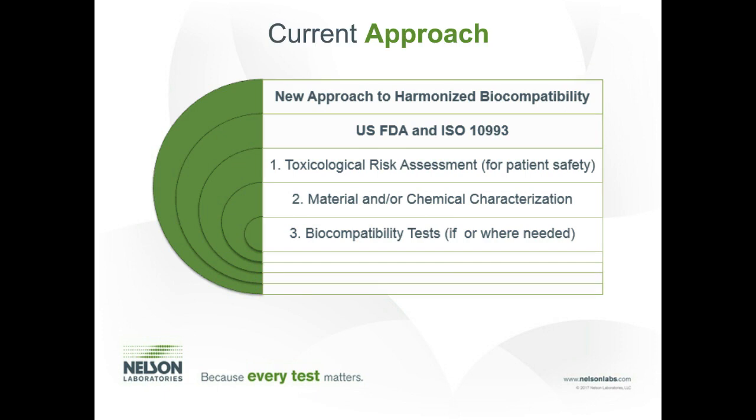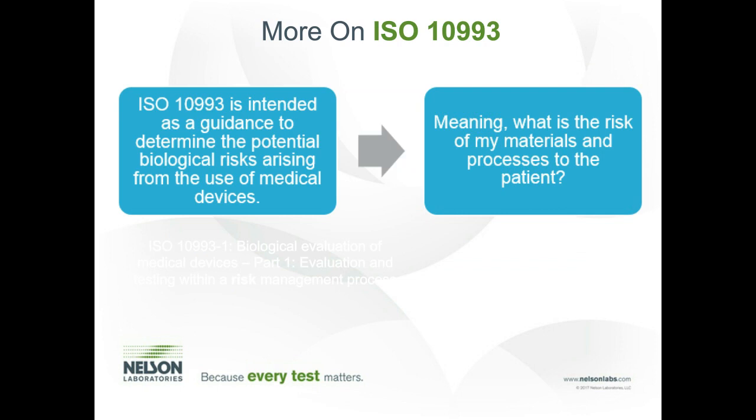But this isn't something that should be new. Most companies, honestly, that I've worked with recently, it's new in trying to implement it into their systems. But if you look at ISO 10993 as currently stated, it's still about a risk-based approach. If you look at how it's written, especially dash one, and the guidance, it really has you evaluate medical devices within that risk management process. It's just we haven't done a great job of implementing this. And honestly, I think it puts regulatory agencies in a hard spot when they feel like there's not been sufficient risk management, just looking at testing by checkbox mentality.